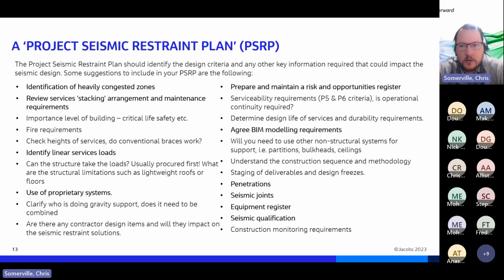Fire requirements are always a challenging one, not just through penetrations, but also what you're supporting off. On CRL we had fire rated cable trays, and looking at how we could support those within a zone where we didn't have fire rated structure was a challenge that had to be worked through.